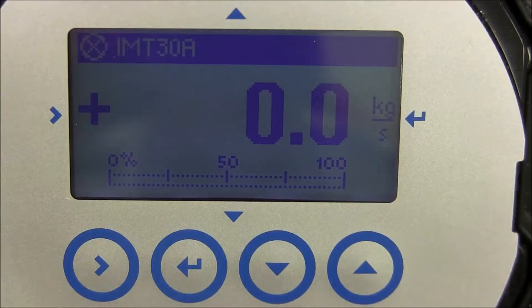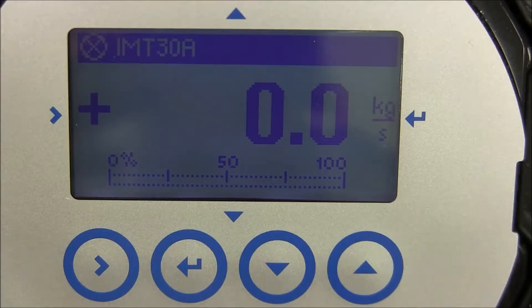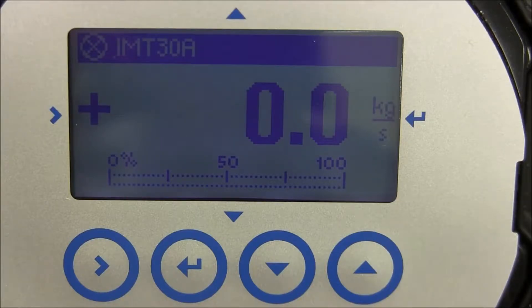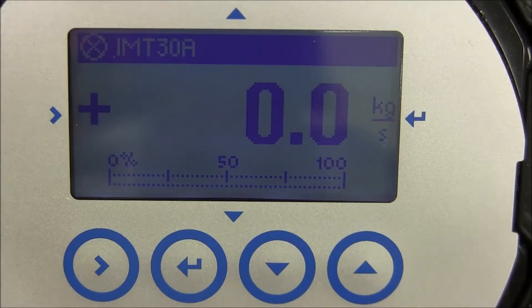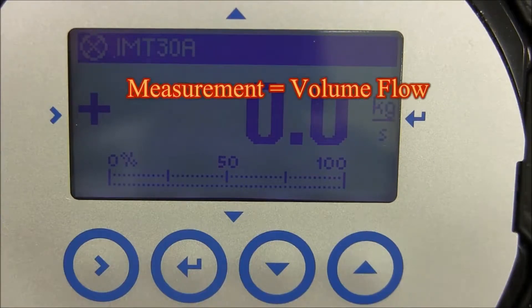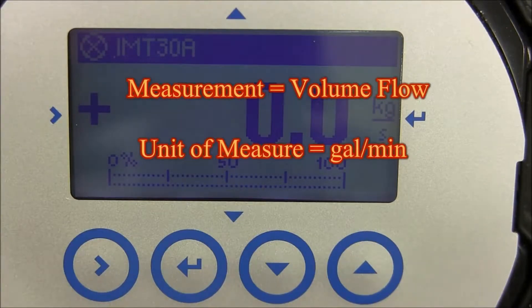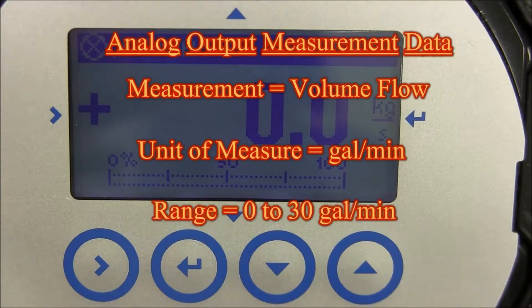I will first enter in three parameters for the analog output measurements: measure selection, unit of measurement, and the range setting for the current output. For this video, I will be selecting volume flow for measurement, gallons per minute for units of measure, and a range setting of 0 to 30 gallons per minute.